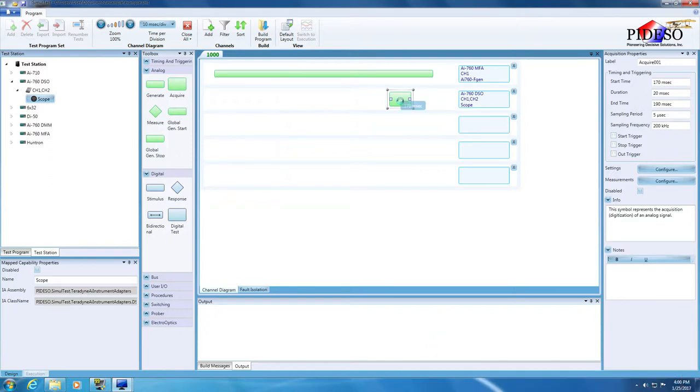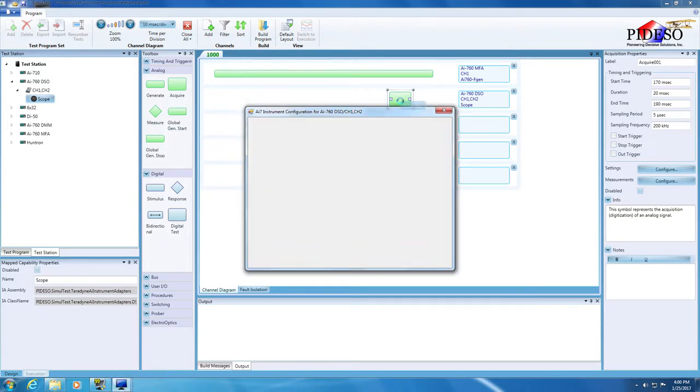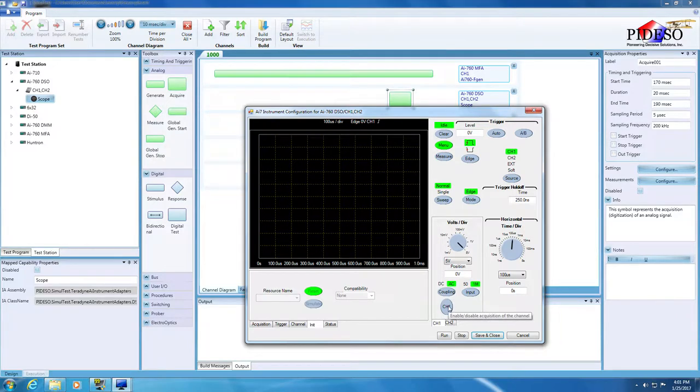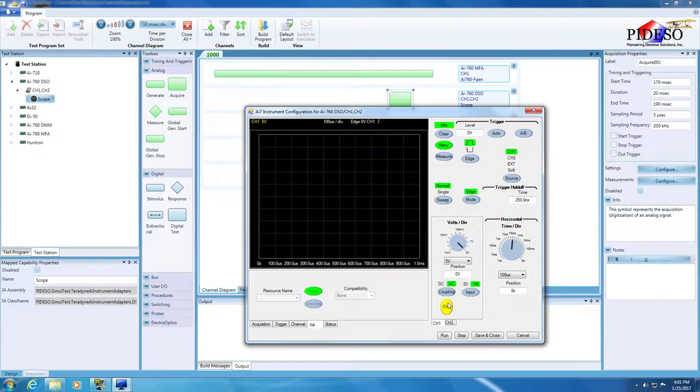Double-click on the new operation to open the AI7 instrument config. I am enabling Channel 1 for acquisition as it is the channel that is physically wired to the MFA Channel 1 on my chassis. Keep the other attributes as they are. Normally you'd save and close, but just like with the other config window, we'll hide it for now by clicking on the main window.